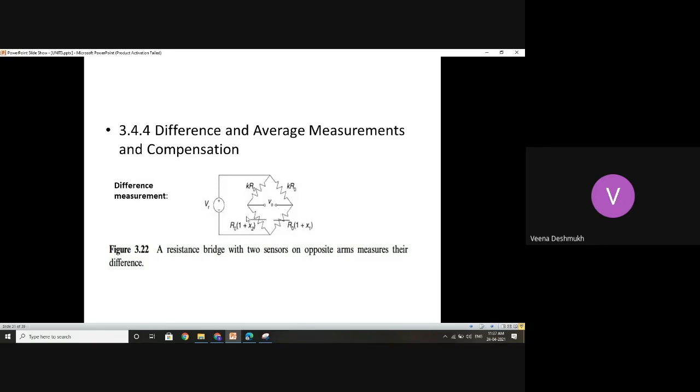So usually under such cases, not only is one bridge measurement used, there is another mechanism always in place to measure the temperatures. And if the difference in these two measurements is found very, very high, then it is checked which one is giving erroneous results. If the differences in these two measurements are considerable, then definitely the entire system of measurements requires some monitoring.